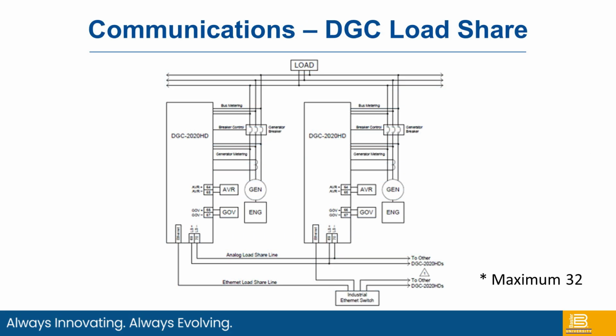We have load sharing lines. We talked about multiple generators in one application, and we have multiple different methods of being able to communicate. As I stated earlier, we have the Ethernet load sharing lines, which you can see at the bottom. Each DGC will go to an unmanaged industrial Ethernet switch and then get daisy chained between DGCs. We also have the ability to do an analog load share line between the DGC HDs, so you can have kind of a redundant system built in. In case the Ethernet lines get cut or the analog lines get cut, the load sharing will continue. We also have a third backup.